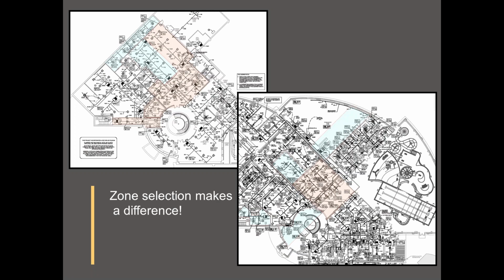How much heat was it recovering? I don't think very much. And if you apply the same logic, the blue zone is all core because it's adjacent to earth, not the outdoors. Here's an interior zone. This is mostly interior with a little bit of perimeter wall, but there's a little perimeter wall with a little glazing here. So all in all, these two units were, although they were specified and installed as heat recovery heat pumps, they didn't achieve their potential because the mix of zones wasn't so effective.